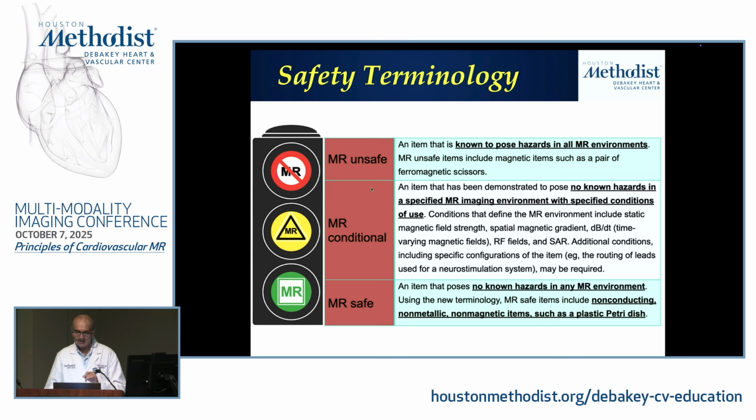MRI safe is something that in any scenario is safe to take into the MRI environment. That's like a petri dish, like a plastic, right? MRI unsafe is something that we know definitely cannot be taken into the MRI environment. That bed you saw, that's definitely MRI unsafe, okay? Most devices that we use today are what we call MRI conditional. What that means is not that it's a blanket, you can take it into the MRI, it's that we've tested it in a variety of scenarios, and in this series of scenarios, it's considered acceptable risk, all right?